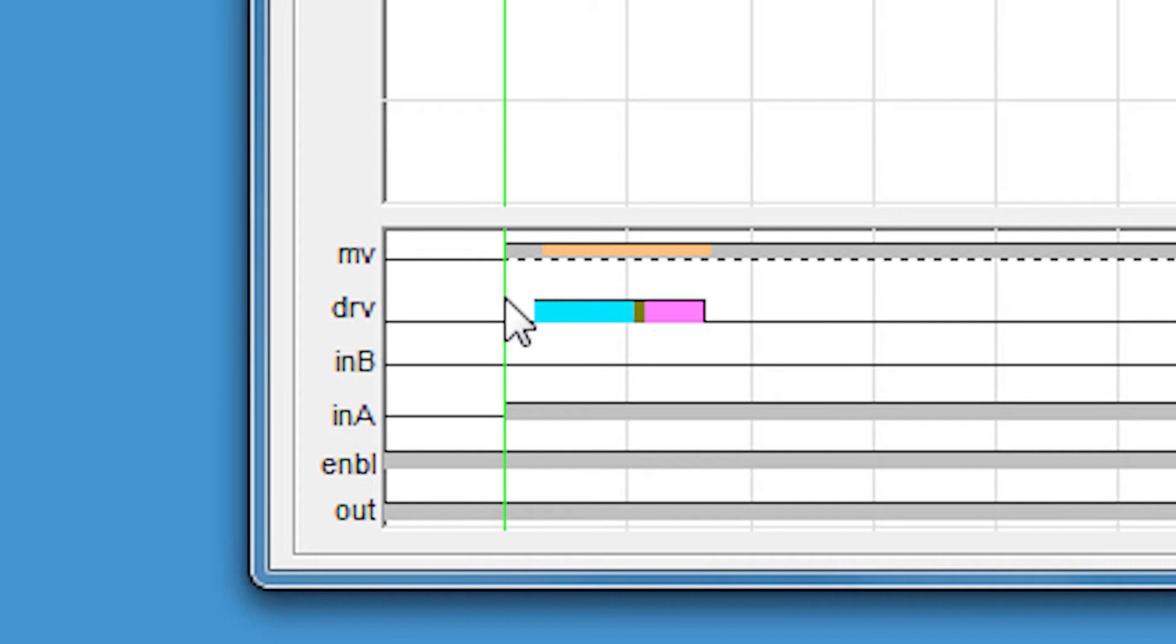The blue line represents torque saturation. If you're unfamiliar with this term, think about what saturation means. It's the point at which no more of a substance can be added. So torque saturation means that the servo is applying all of the torque that's able to apply, either due to a limit of the motor or a user imposed torque limit. If you make a move that requires more peak torque than the motor can apply, the torque saturation indicator will turn on like it did in this case.